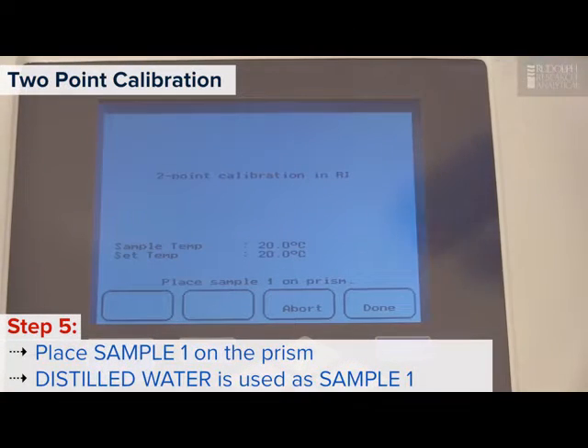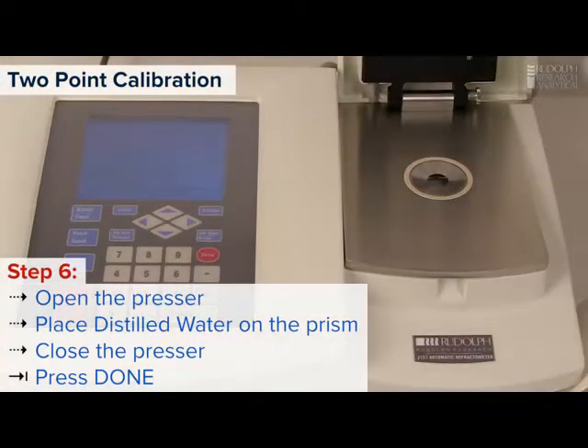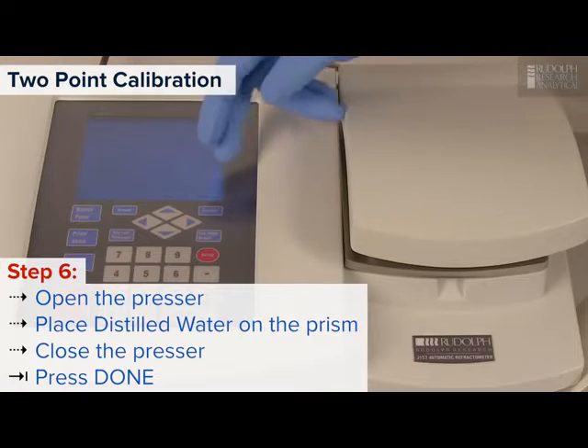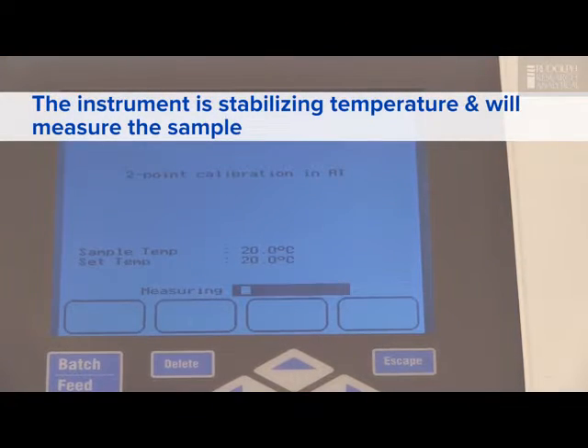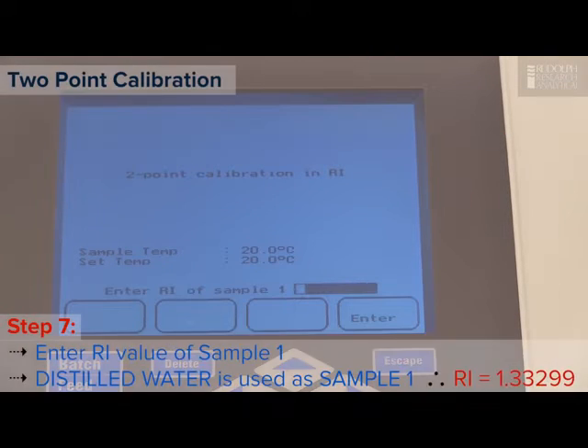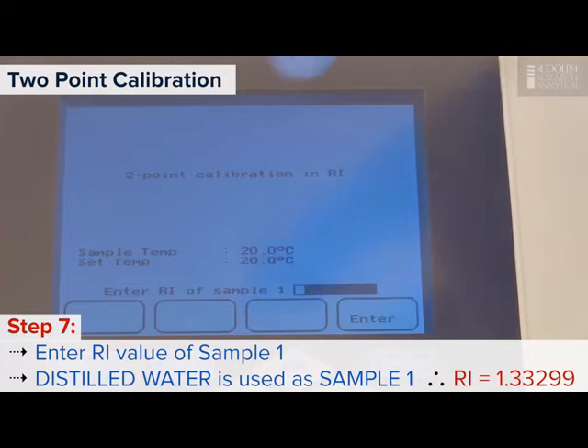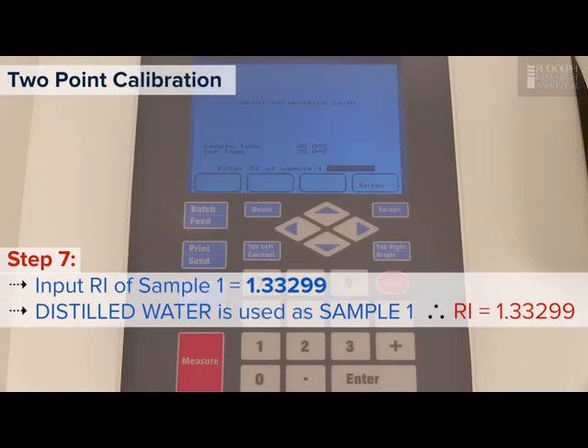Now the refractometer is going to ask you to place sample 1 on the prism. Sample 1 is going to be distilled water. So open up the presser and place distilled water on the prism and close the presser. And now press Done. The instrument's going to be stabilizing temperature at 20 and now it's going to be measuring the sample. Now, after it measured the sample, it's going to ask you to enter in the refractive index of sample 1. It is known that the value of water at 20 degrees is 1.33299.